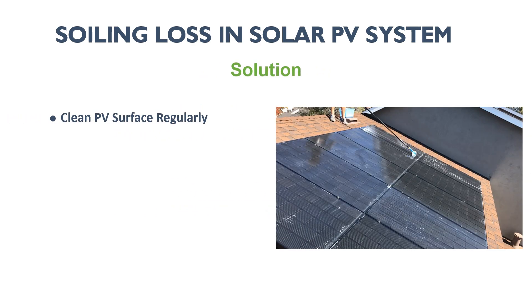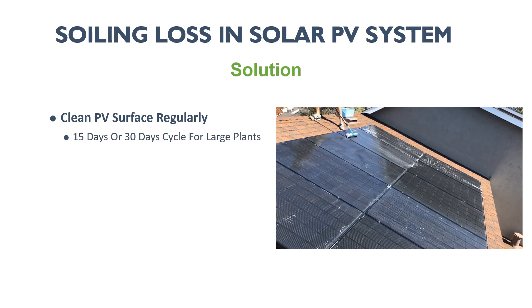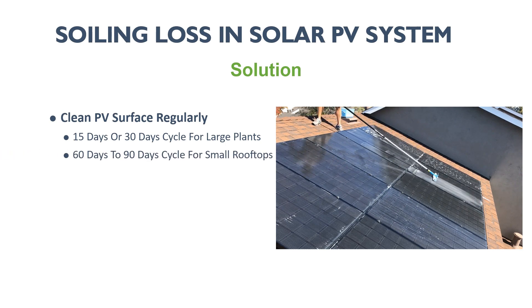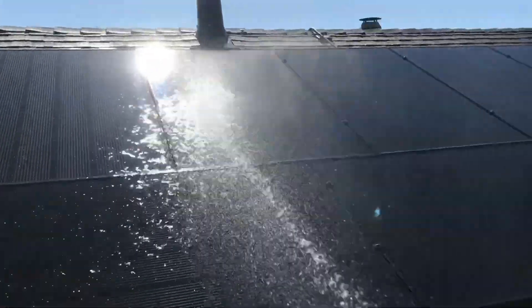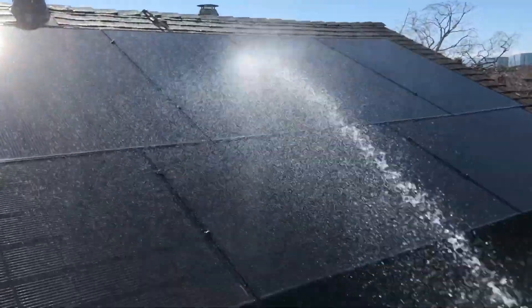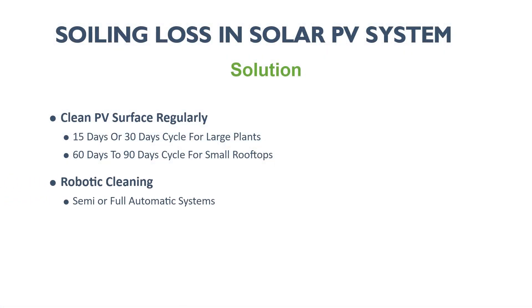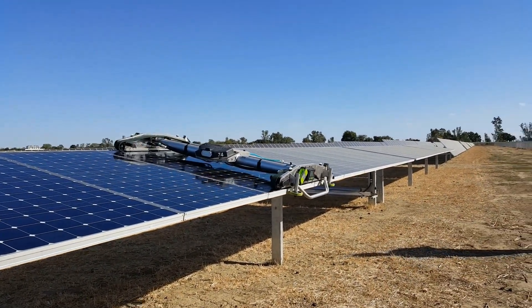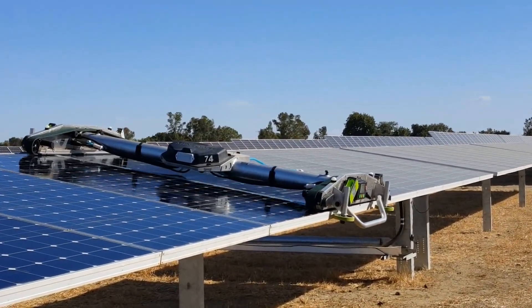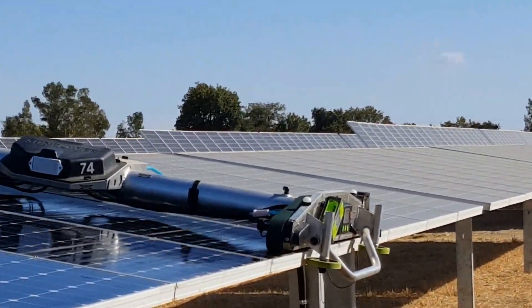To reduce soiling loss, the only option is to clean the PV surface regularly. For large-scale solar plants, a 15- to 30-day cleaning cycle is normally followed. For smaller systems up to 100 kilowatt-peak rooftop systems, one can follow a 60- to 90-day water-based cleaning cycle. Nowadays, robotic cleaning is very popular in the PV market, and implementing robotic cleaning into your plant is a very good way of preventing soiling loss.